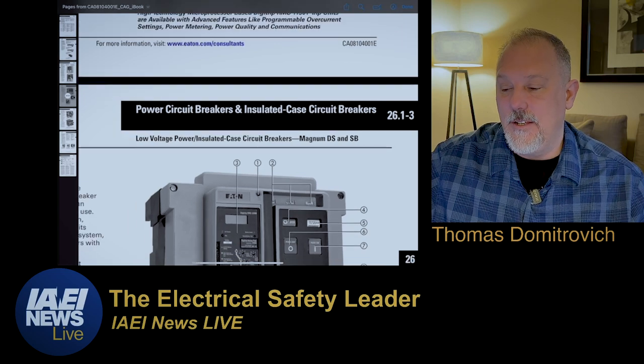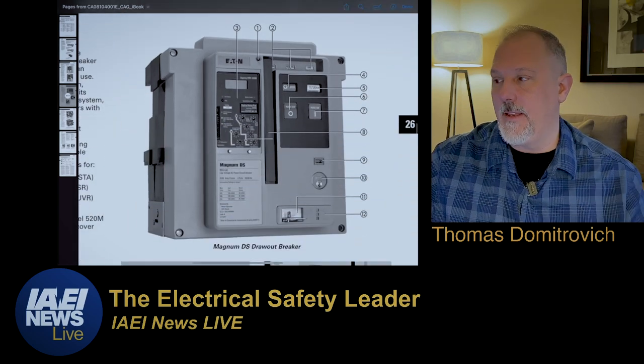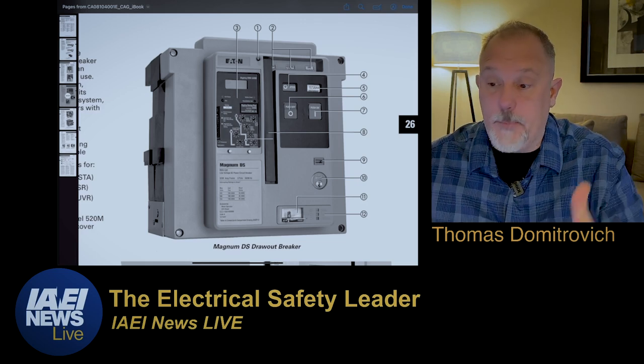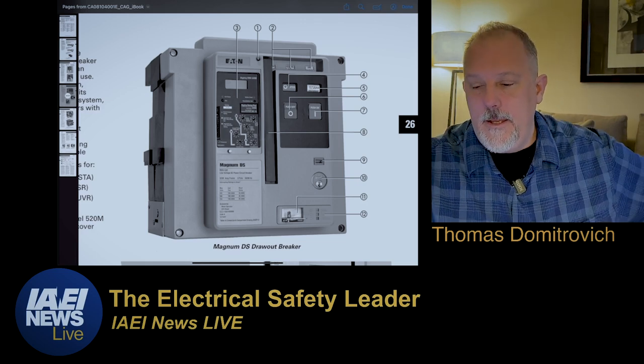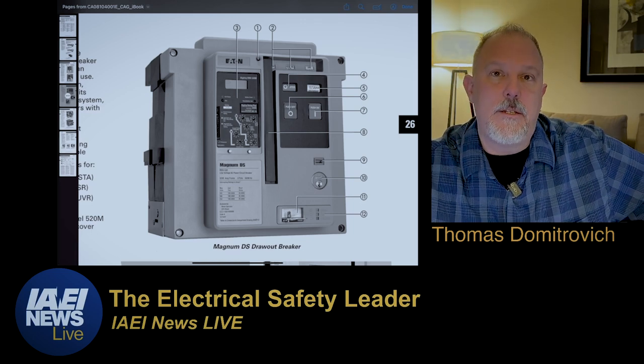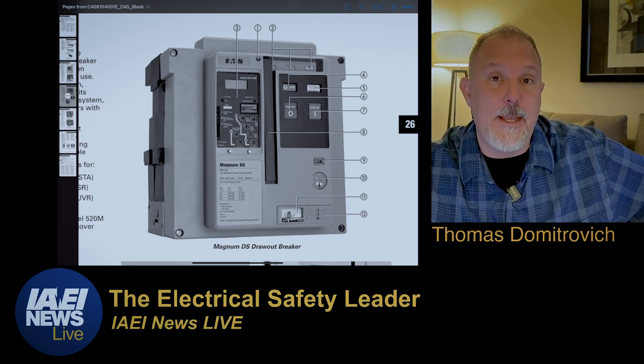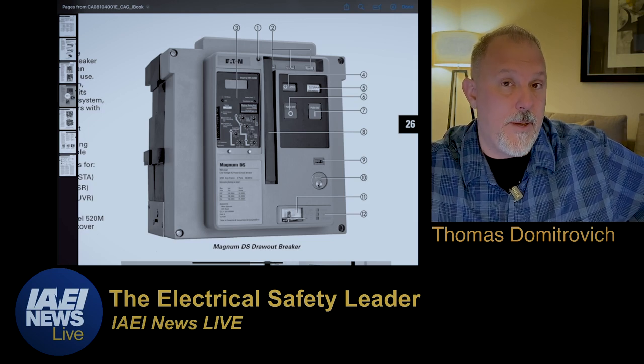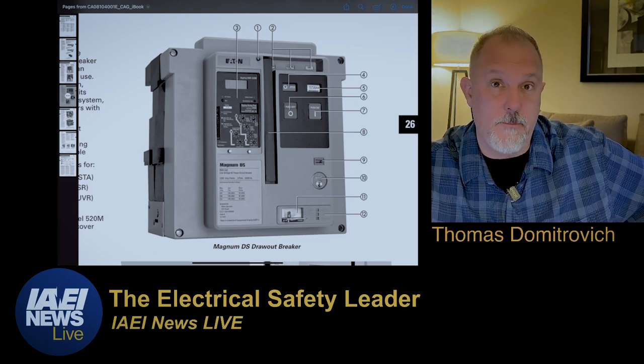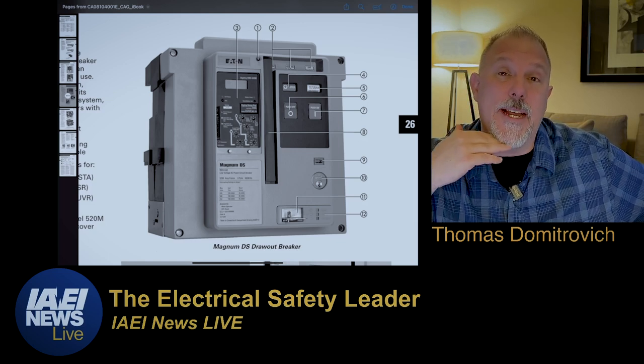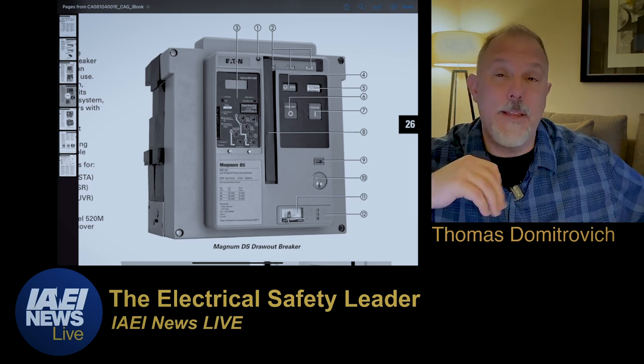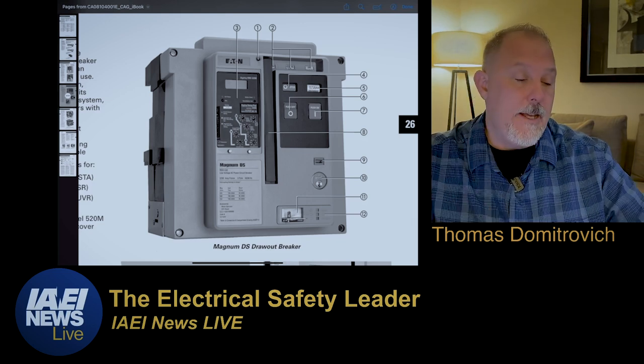So here's the issue. You take a breaker like this, and these are big beasts, okay? This circuit breaker, I can list it to UL 489 as an insulated case circuit breaker. It's not a power circuit breaker. I could take that same circuit breaker and list it as a power circuit breaker. Now, there are a few breakers that I can do that with, that any manufacturer can do that with. And what that does is it blurs the lines when we start talking about what can and cannot be reconditioned.